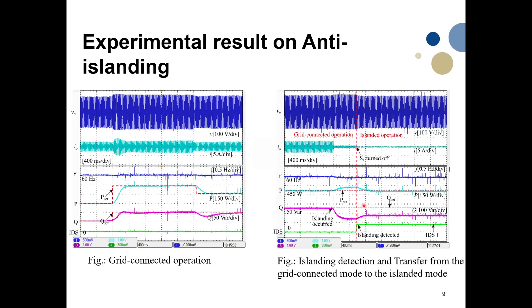When islanding is detected, the system disconnects the grid-connection circuit breaker, isolating the microgrid from the grid and supplying power to the local load. The current to the grid becomes zero, but the inverter still maintains voltage and supplies power to the local loads — here the local load is 450 W. We also see that the inverter, which was supplying 50 VAR of reactive power, is now consuming some reactive power.